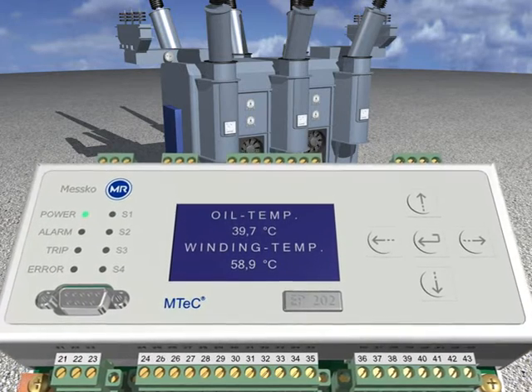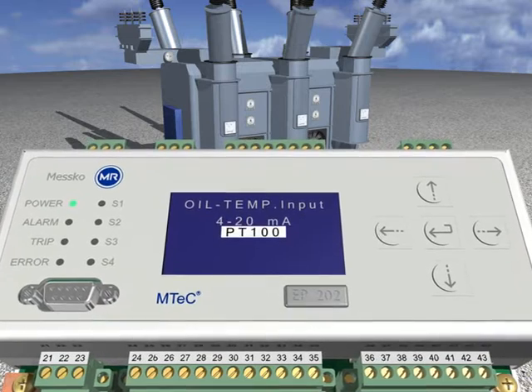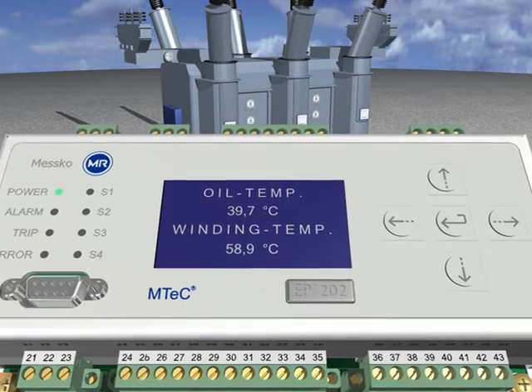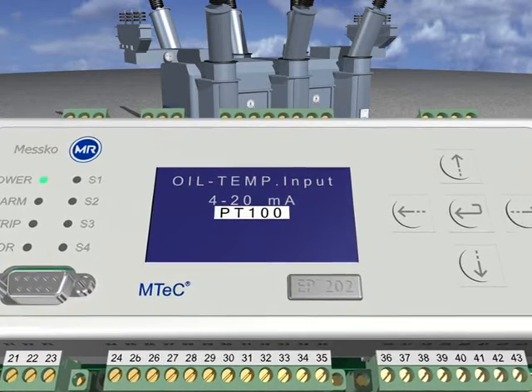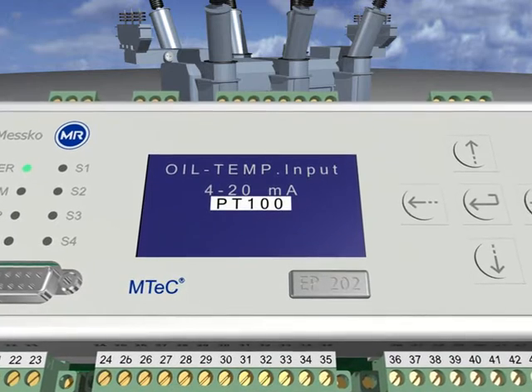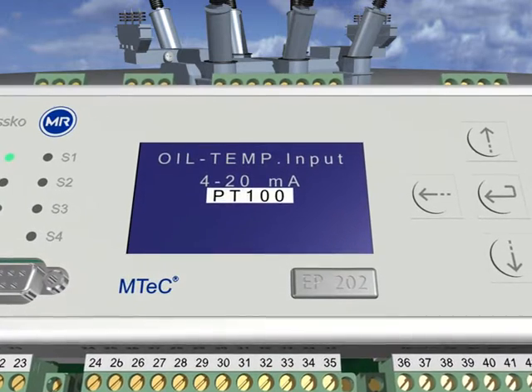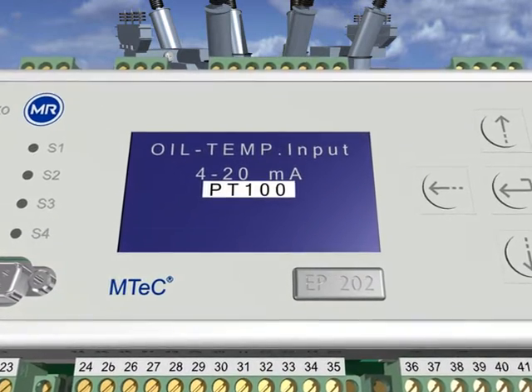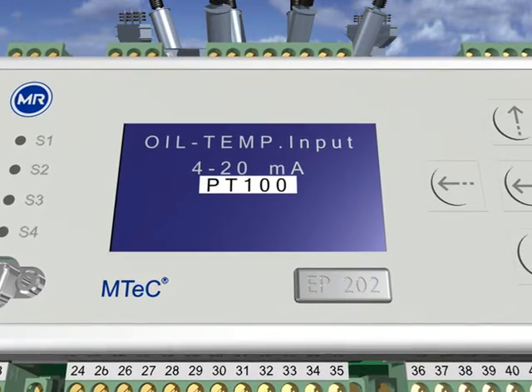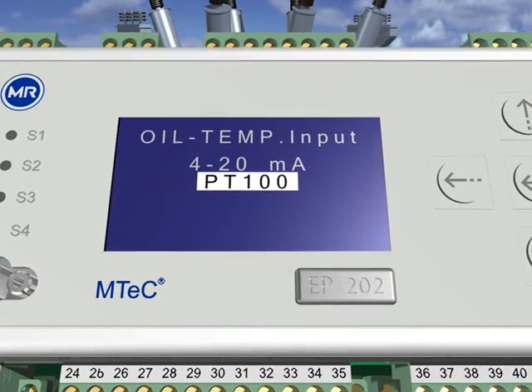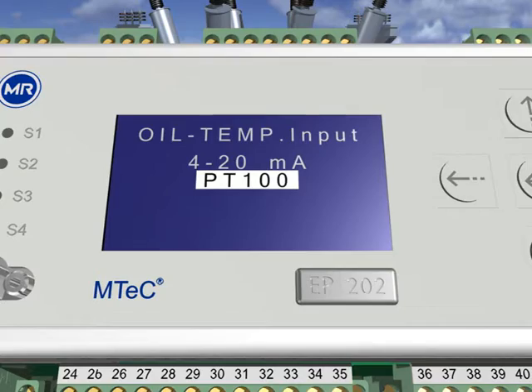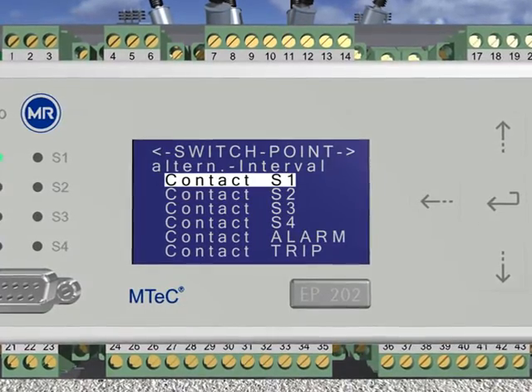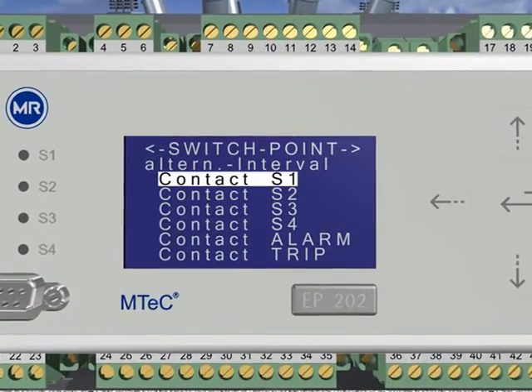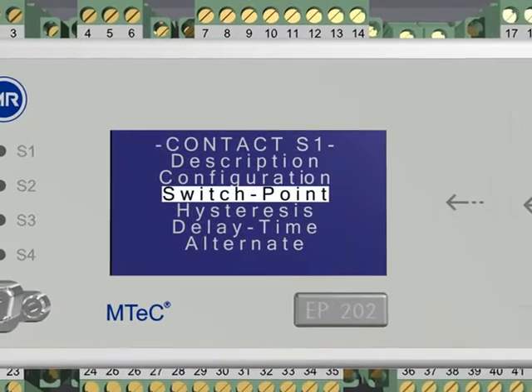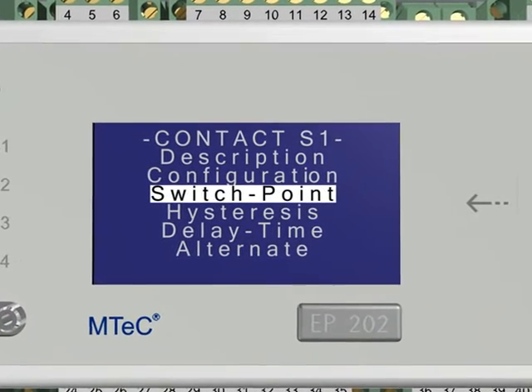Based on which sensor you use for measuring the top oil temperature, the input parameterization can be selected as desired. The outputs of the MTeC can also be set as desired. If you want to connect another device later on, just parameterize the output again. You can configure the individual switching contacts so that they are allocated to either the oil or the winding temperature. In addition, you can switch each fan group by hand.